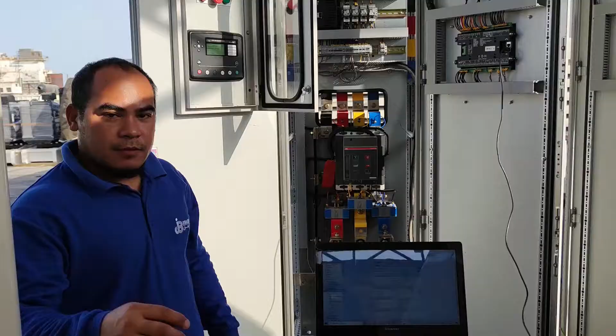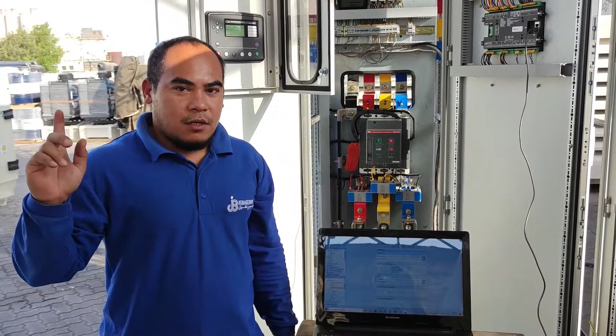Okay guys, now we're going to start the generator, generator one, the set one I mean. We're going to start and simulate the breaker close and breaker open. So we are already done and trying to test the biasing. Now it is working, so I will show you how to start the generator so we can see if the breaker is closing or not. So you can actually see.